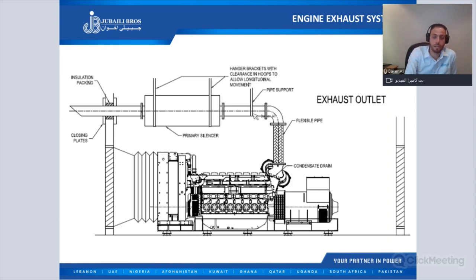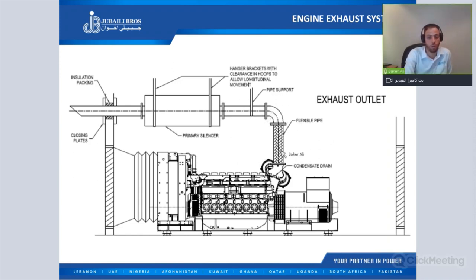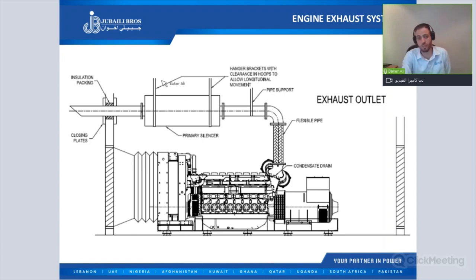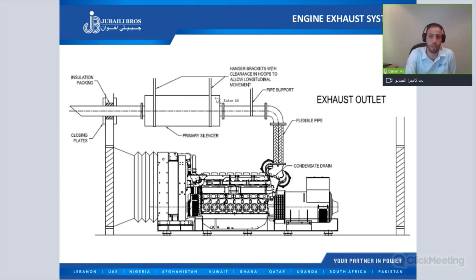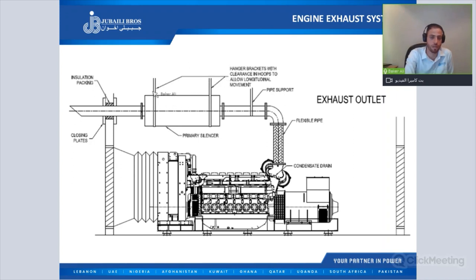The exhaust system must have enough support for the pipe to avoid any weight from the exhaust system loading onto the engine. For the silencer, we recommend fixing spring hangers on the brackets to avoid vibration transmission from the silencer to the building. This is very important — spring hangers must be fixed to avoid vibration transmission from the silencer to the building.